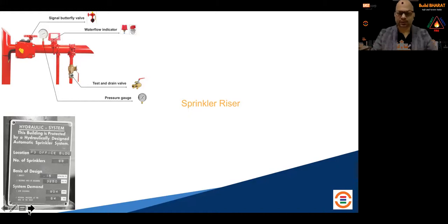Sprinklers have too many problems, too many issues, because it's one of the most complex systems on earth to design, and on top of it, it has to be implemented. Most places design the sprinkler system with just the pipe schedule method - that means a 1-inch pipe, 2 sprinklers - and that's how the pipe schedule method is allowed in the code and standard. But technically, that's not a requirement. Your requirement is that in the shop drawings, you are able to produce calculations justifying the demand and supply of the entire piping, how the distribution is going to happen, whether you get the remotest optimum flow and pressure, and that is what your calculation is going to demonstrate.